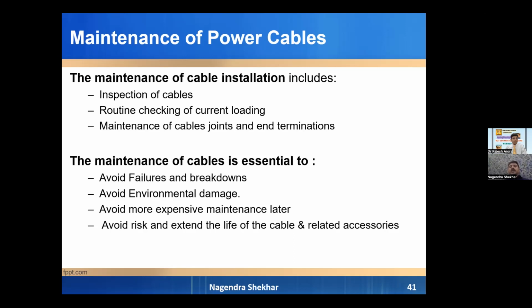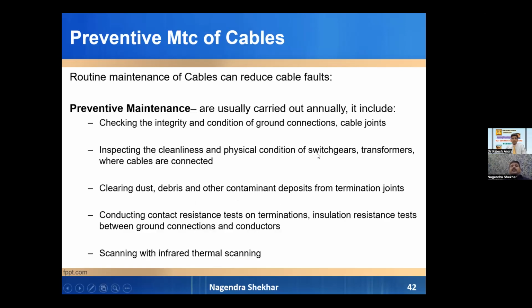Because to avoid failures and breakdowns, environmental damage, every cable damage means damage to the environment because of digging, damaging the tree roots, and the PVC and epoxy which are used. It also means more expensive maintenance. When we have to replace a cable termination joint, we can replace it without replacing the cable. But once it is burnt badly because of a fault, we have to replace the cable also. Again, we have to increase cable life and the life of accessories.